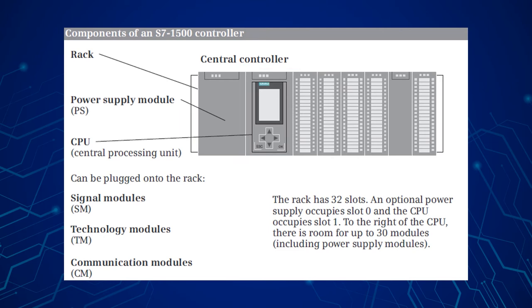The power supply modules provide the internal voltages required by the programmable controller. Up to three system power supply modules can be used in the programmable controller as needed. Load voltages or load currents are provided via external load current supplies, which can also provide 24V primary voltage for system power supply modules.